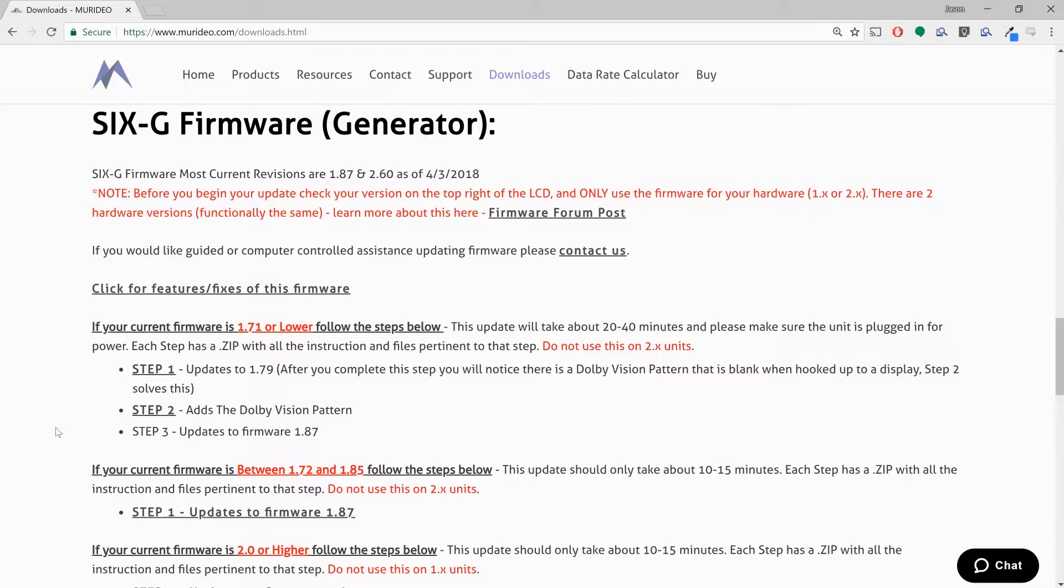And there it is. Now before when I mentioned figuring out the firmware that the generator currently has on it, that becomes very important right here. There are two different hardware versions of the 6G generator. So your firmware is going to start with either one or a two. Now if you're at firmware 1.71 or lower, you will have to do two firmware updates.